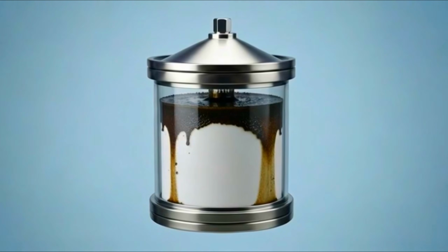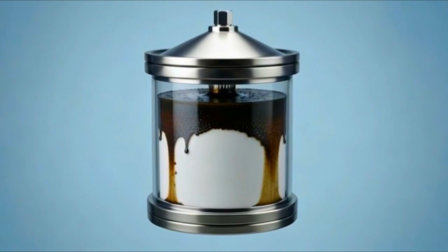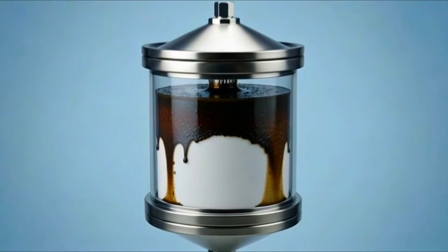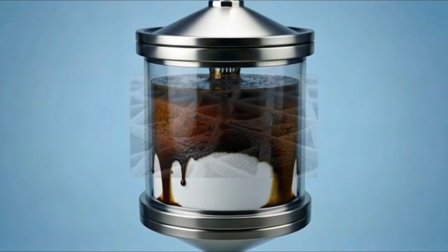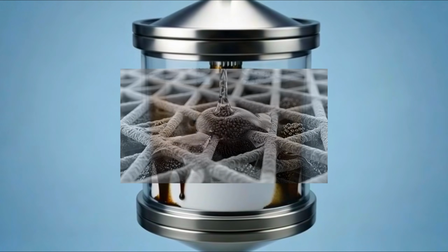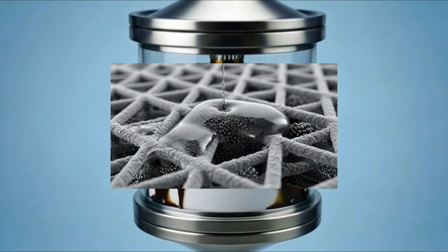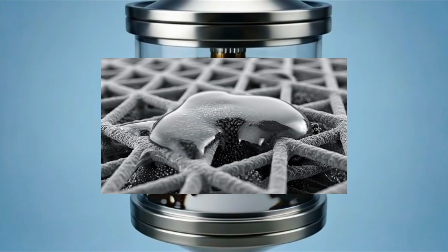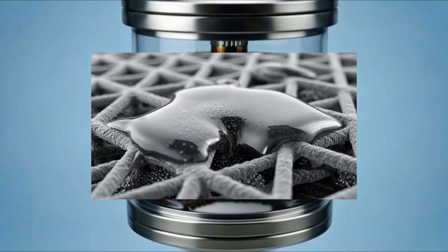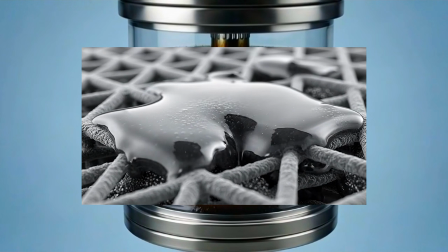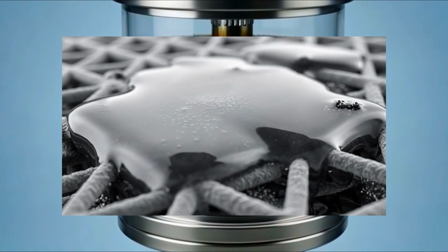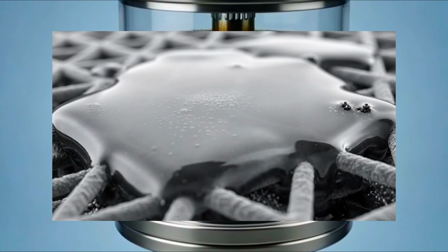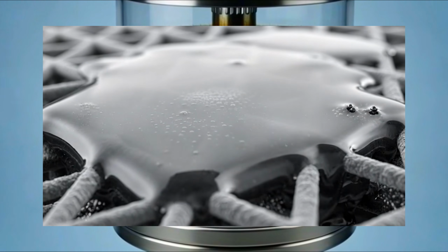The oil is passed through the bypass oil filter cartridge according to the radial flow principle, from the center outward to the periphery. Solid particles larger than 1 micron cannot pass through the cellulose fibrous structure of the cartridge. While water droplets are absorbed and trapped by the cellulose, the oil flow continues. Very fine residues that are able to pass through the filter cartridge are then retained by the safety plate at the bottom of the cartridge.